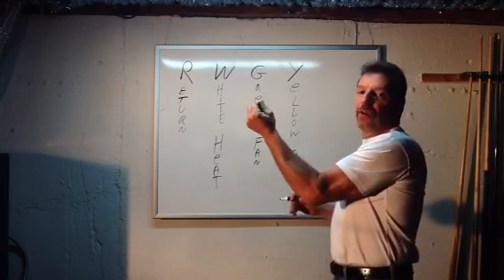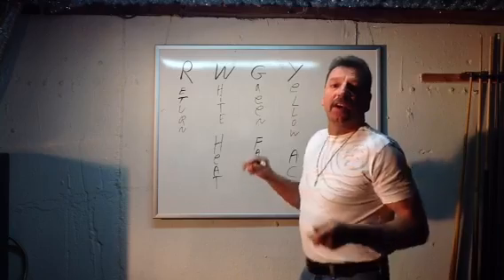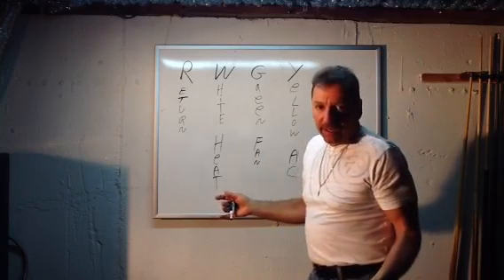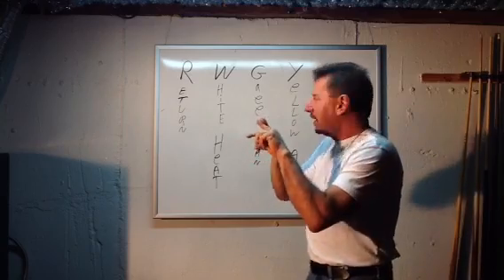That red wire controls everything. If you twist the red and white together, the heat would come on. That's what the thermostat does when you turn it up—it touches the red and the white together.